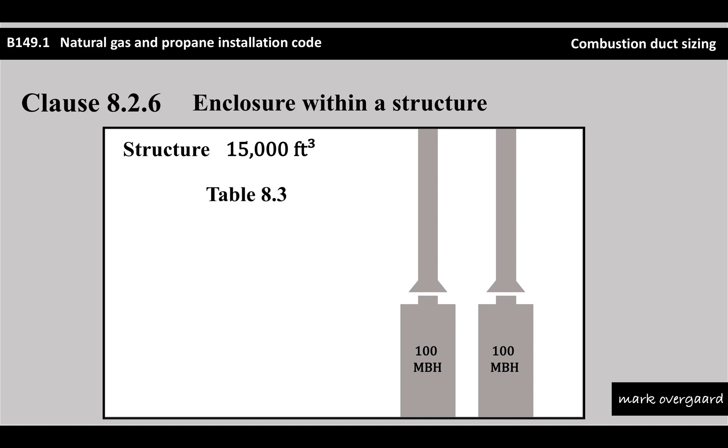If we were to size the opening in the wall that you might need to feed these appliances, we would go off Table 8.3. Table 8.3 is for low volume, a leaky structure with draft control. With 15,000 cubic feet and 200,000 BTUs, you don't need any extra openings. That's part of the whole clause - this structure has to be able to handle these two appliances with enough air coming in through the leaks and cracks.